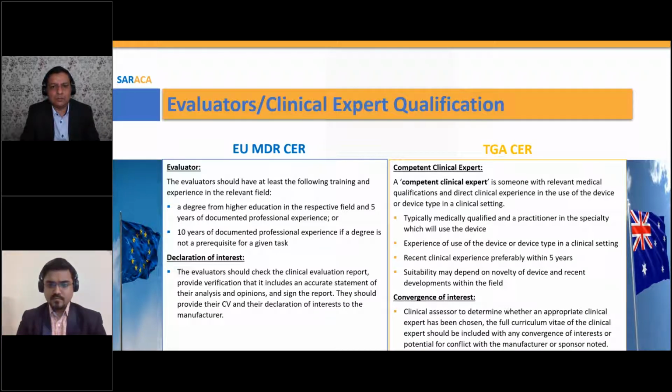In TGA, it's a little different. The clinical assessor is to determine whether an appropriate clinical expert has been chosen. The full curriculum vitae of the clinical expert should be included, with any convergence of interest or potential for conflict with the manufacturer or the sponsor noted. Would you like to explain that a little bit in more detail, Arun? I think that's an important difference.